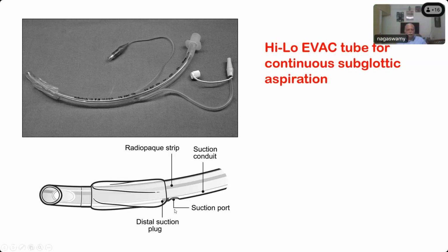So the suction tube you can see is opening just above the cuff. So all the secretions which are likely to drain down through the small gaps that will happen with the high volume cuff going down, you suck it even before they can travel down. So the suction port ends just proximal to the cuff, and you can periodically suction to prevent ventilator associated pneumonia.